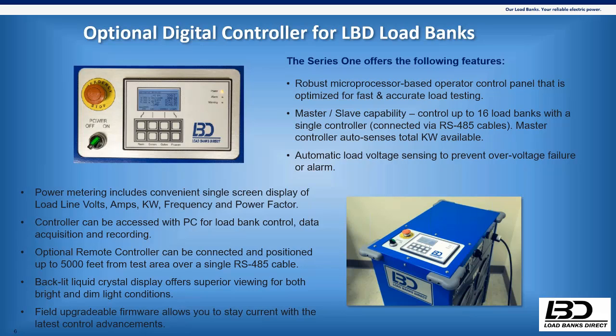Units with these digital controllers also have all the same safety circuits that our manually controlled load banks have. It's just displayed a little bit differently on the controller itself. Another awesome feature of this Series 1 digital controller is voltage correction. Say you're running a test at 480 volts and your voltage dips a little, so your amp draw goes up. This will automatically correct, turning steps on and off, to keep your load within, I want to say 3% is the number, of the desired value.